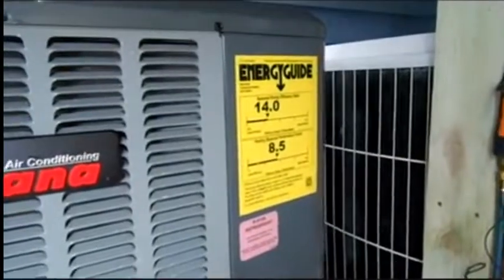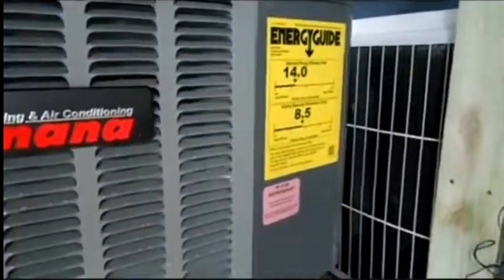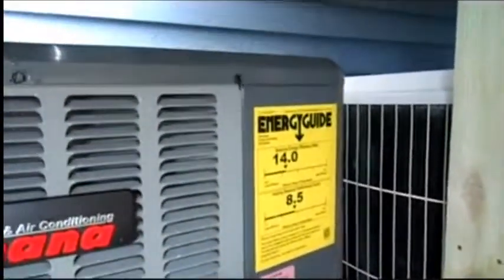Alright, we are pulling our vacuum. We're almost done with the vacuum. It's pulled down to 230 microns. We blanked it off. It keeps coming down and coming down. I want to make sure this is a nice dry system because, you know, with the retrofits, you never know what went on in the last system. It was blown out with Pro Flush. I want to make sure all the Pro Flush is evaporated out of the line set.